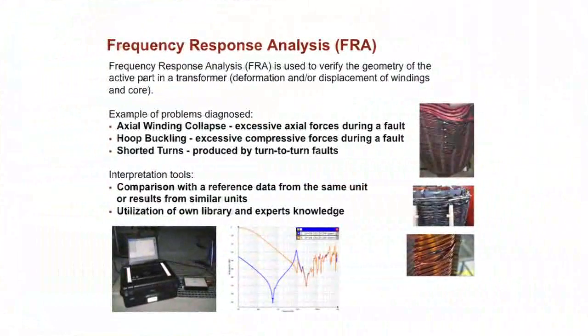And then you put your partial discharge measuring equipment and then you can find the issue with the transformer. There's also SFRA and DFR, so I'll jump to these. So FRA, this is a very popular tool right now. What this is, you put a voltage in and you measure a voltage out, but you do it across a frequency spectrum. And with this, you can see if there's been geometric changes in the windings.